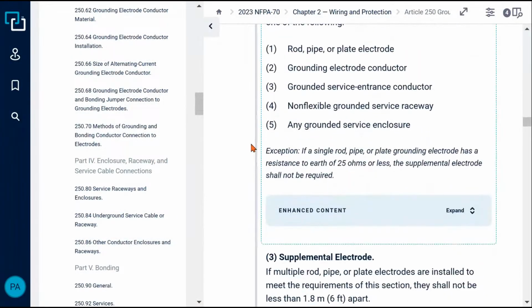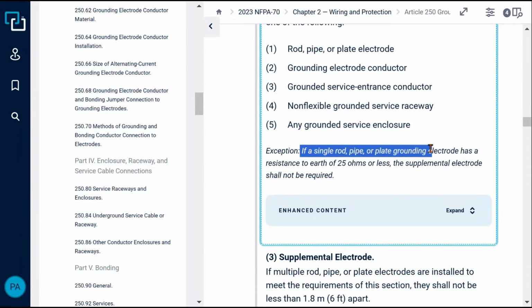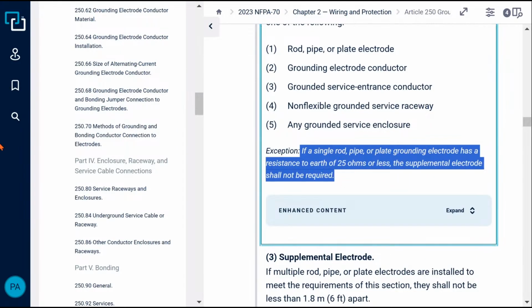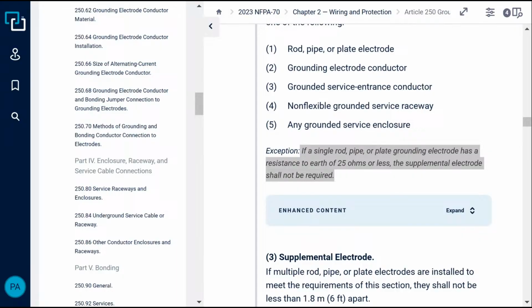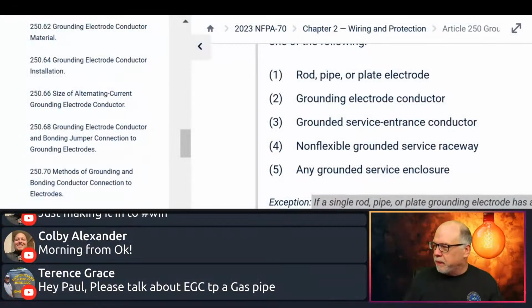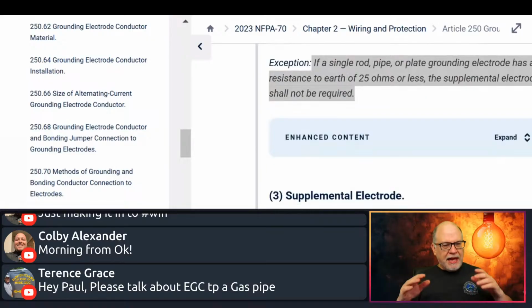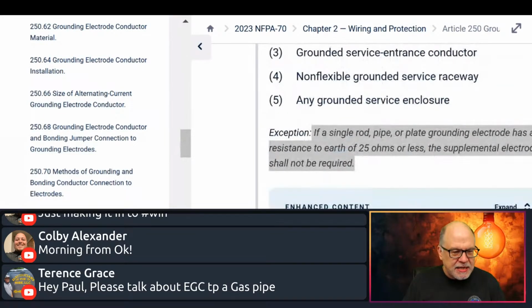Now here's the exception. It says if a single rod, pipe, or plate electrode has a resistance to earth of 25 ohms or less, a supplemental electrode shall not be required. That's important language, folks. Why is that important? Because it pretty much tells us out the gate that we have to do what...